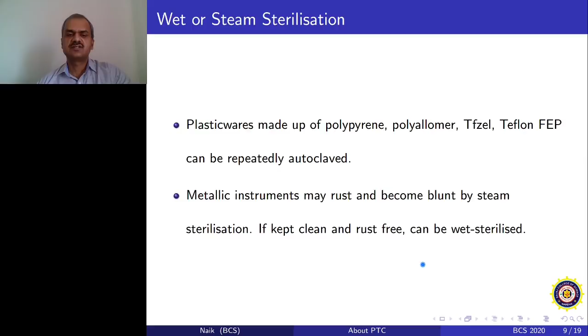If you keep a sandpaper in your lab, sandpaper is the paper which is basically used to scrub the walls when they do painting. That sandpaper is really good if at all you get rust on your forceps or blade holder. You just scrub it and that rust will go off, and you can again autoclave this. But generally these metallic instruments can be sterilized with dry sterilization as well. So both wet as well as dry sterilization work with these tools. Okay, if you keep them clean and rust free, they can be wet sterilized as well.